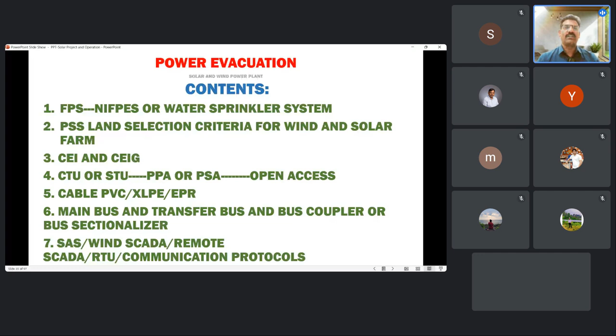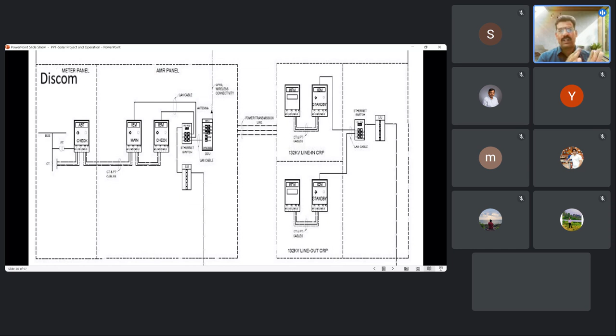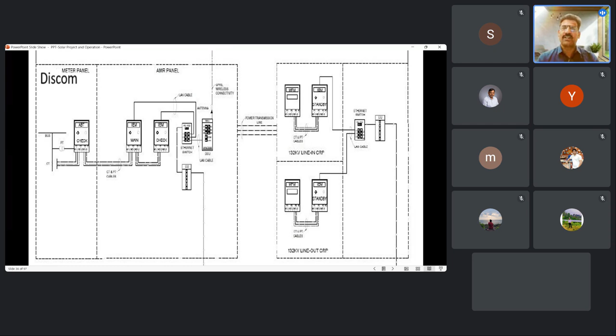This is the AMR scheme, automatic meter reading. This is the check meter, this is the discom meter. For AMR, the meter data is sent to SLDC. Any load dispatch center requires real time data. For that we take the CT from this check meter, which is for commercial billing. All are ABT meters, but for commercial, discom maintains that one - they are sealed, but these meters are not sealed. Through the AMR panel, data goes through DCU, data concentrator unit, and is sent to SLDC. You can see.